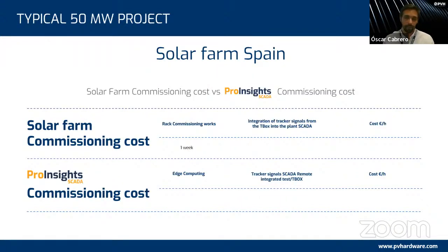Apart from that, regarding the EPC and construction part of the project, a traditional SCADA would cost around 120 hours times the cost of commissioning, because we assume about 1 week to start up the rack and 2 weeks to integrate all the tracker signals with a third-party SCADA. With our solution, there is no cost in terms of commissioning works, and we need only 2 days to integrate all the signals from the trackers into the pre-installed SCADA, which is much less than what a traditional SCADA would require.